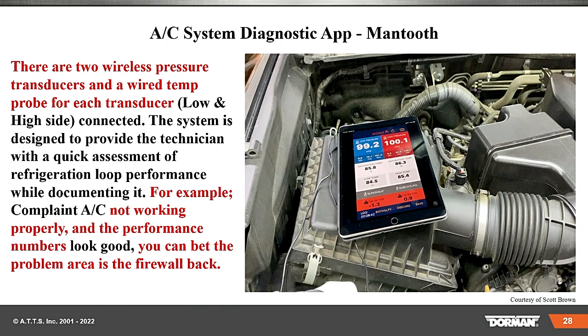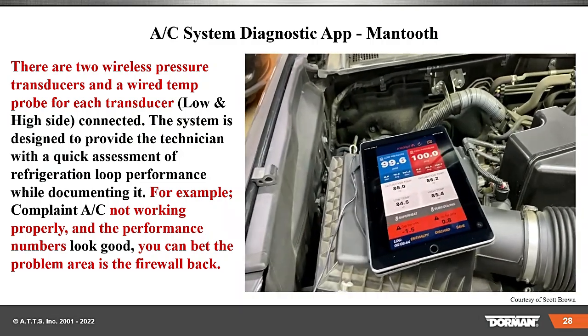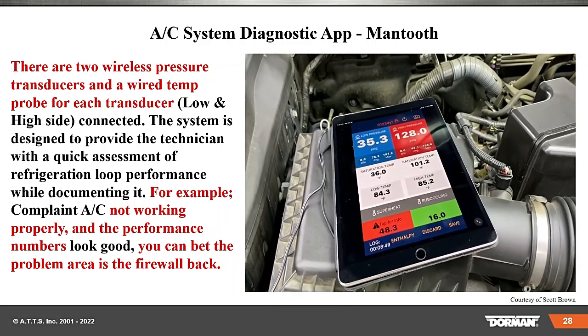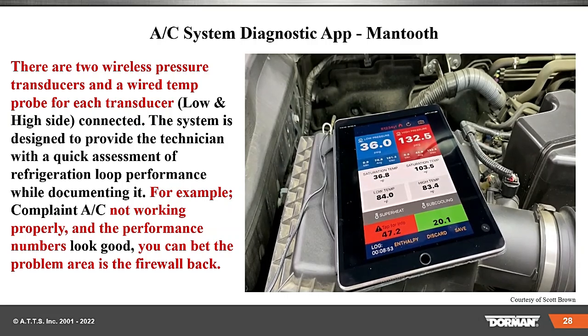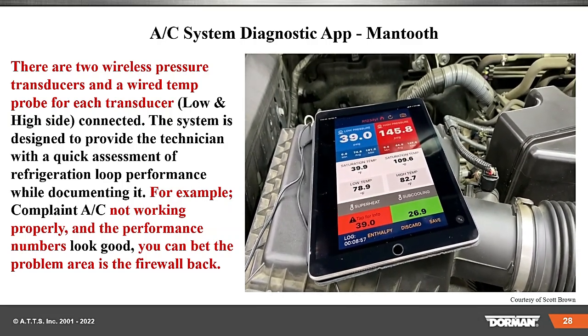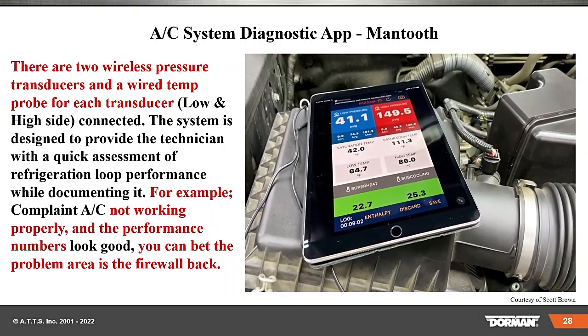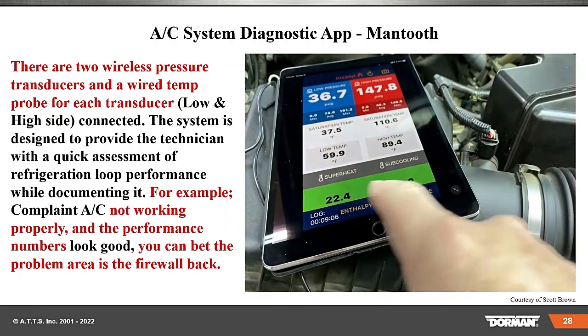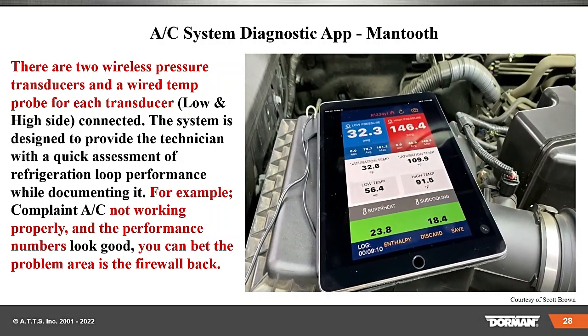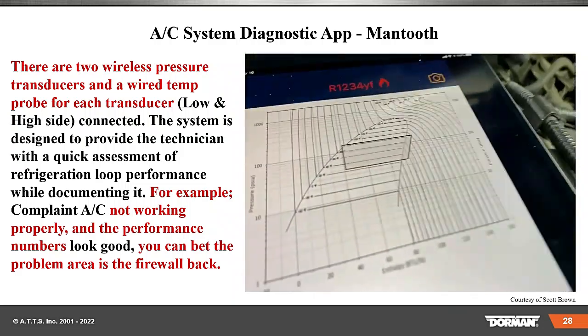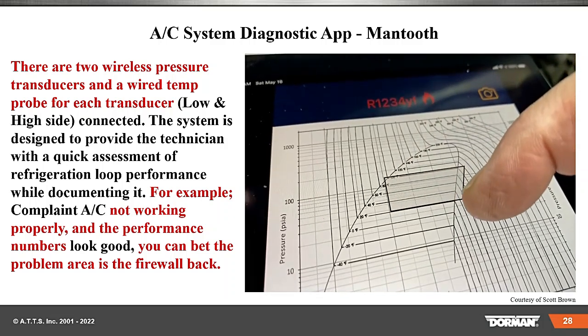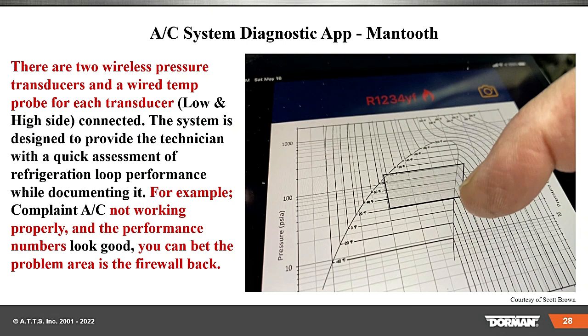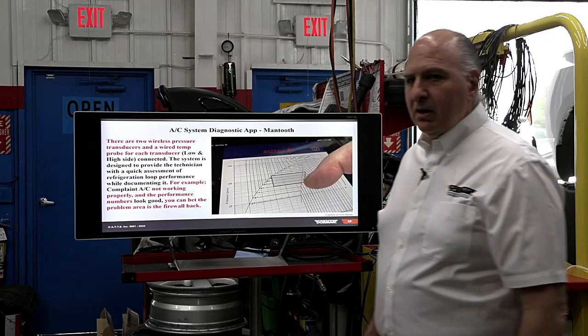We'll play this little video real quick. Take a listen. So here we have both the high side and low side pressures equal, so the system is basically under its equalization status. And here we're going to start the vehicle. So equalization status means the system was not running. They're roughly equal. These are pressure transducers. We have two temperature inputs, and the system is doing calculations for us, primarily looking at the subcooling and superheat there at the bottom two rows. You'll see the superheat on the left. That is the evaporator boiling, right? And then the subcooling is the condenser, as it's condensing that gas into a liquid. And then here we're looking at what's called an enthalpy chart, which is a thermodynamic performance of the refrigeration loop. Make a long story short, thanks to my buddy Scott Brown here for doing that video.